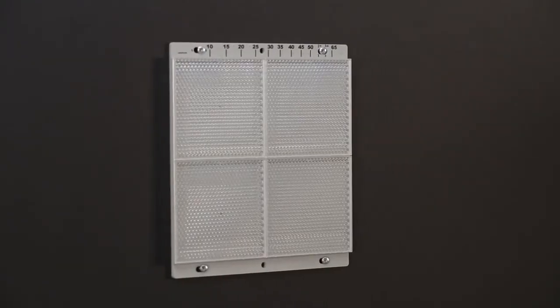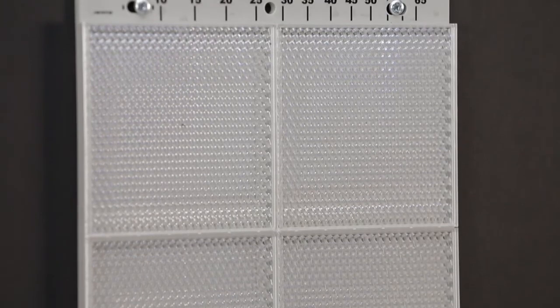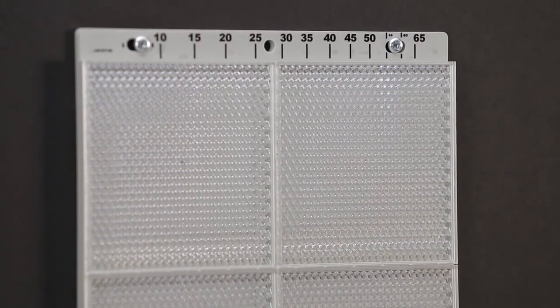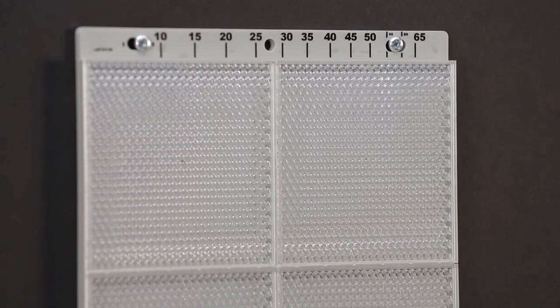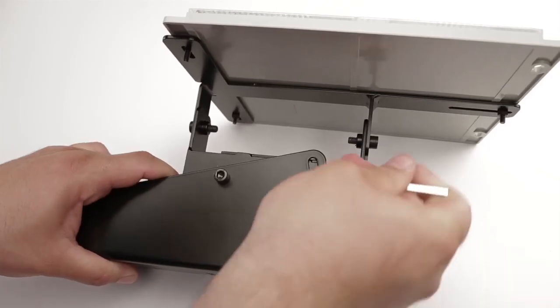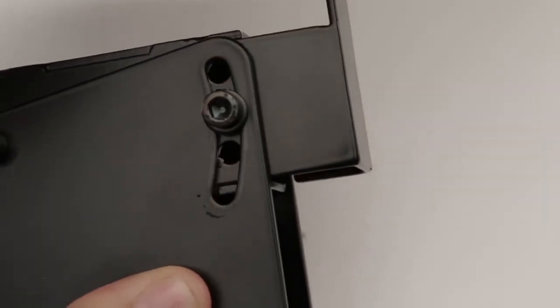Securely mount the reflector on a similar stable surface. Ideally, you should mount the reflector directly across from the detector. If you are not able to mount the reflector within 10 degrees of being straight across from the detector, use the multi-mount kit so that you can aim the reflector directly at the detector.